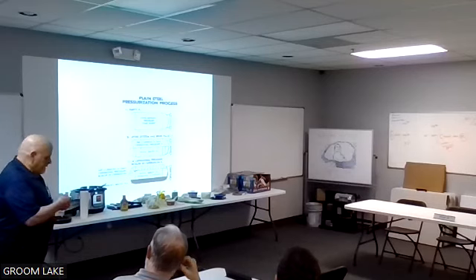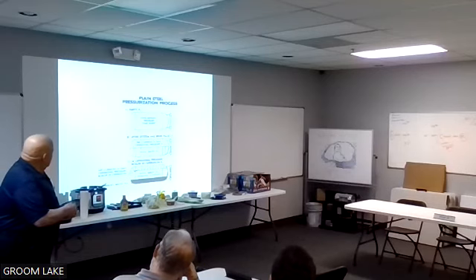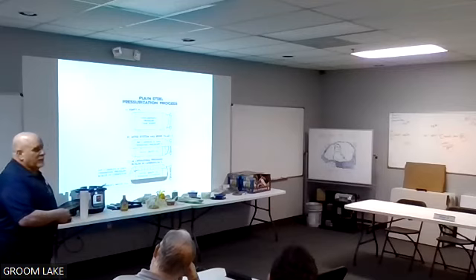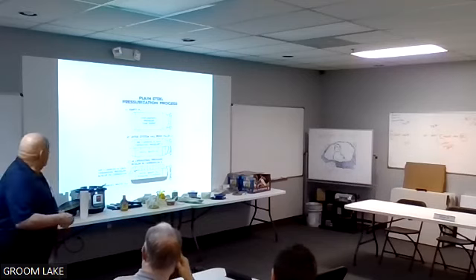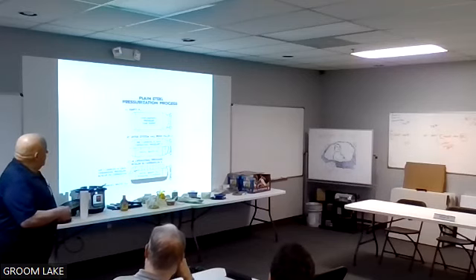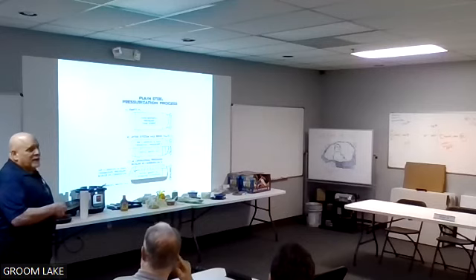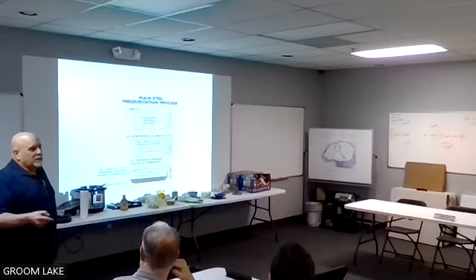And again, here's what we were talking about. Here's your tank empty, here's our air cushion, that's your initial water flow. It's going to fill part of that tank till it equalizes, whatever your fill pressure is. Then you only have this as your expansion volume. So if your tank starts off way high, it's going to run out of expansion room very quickly.